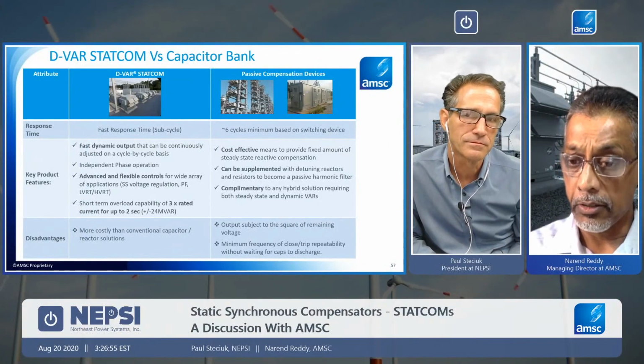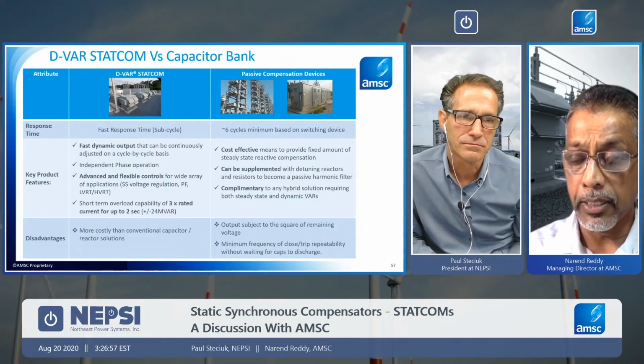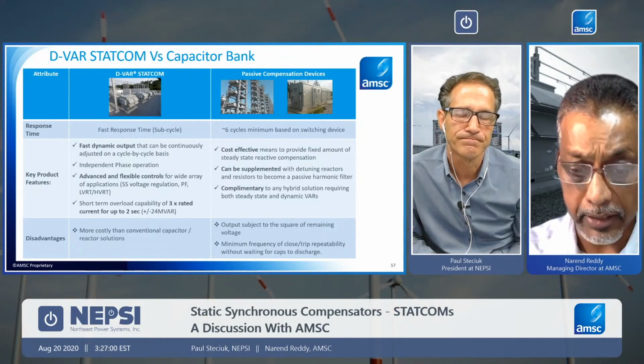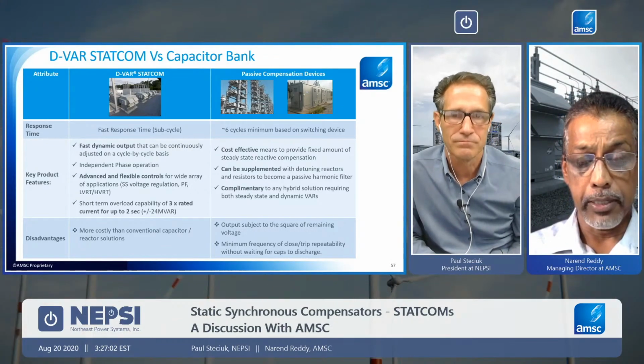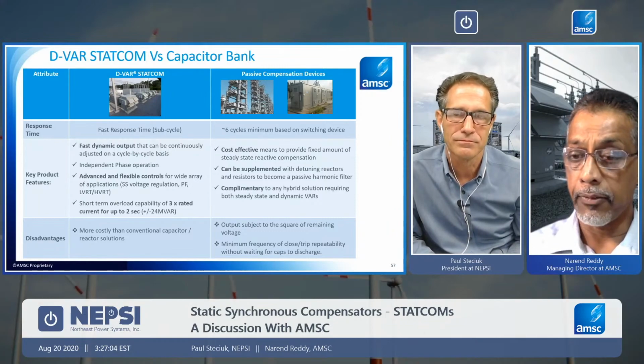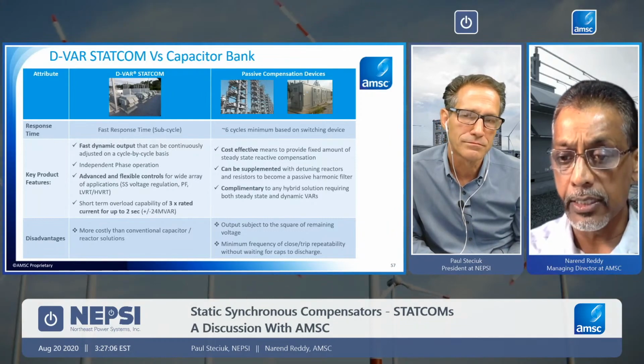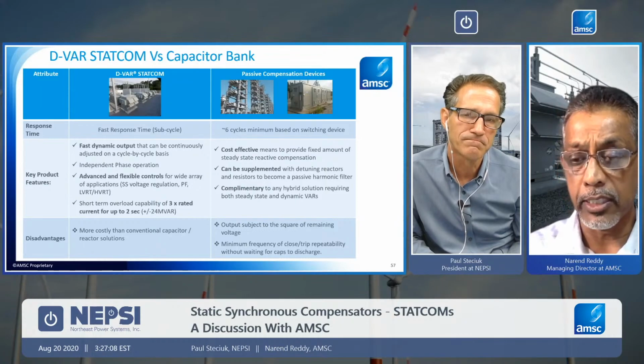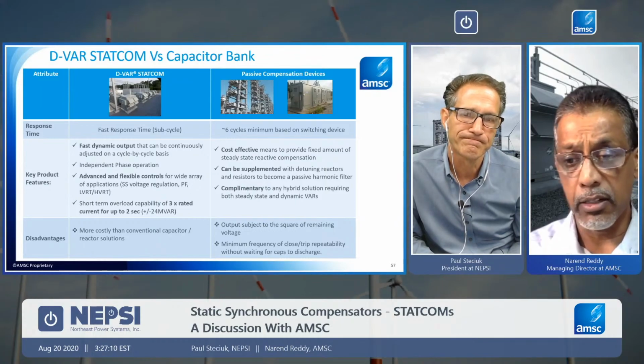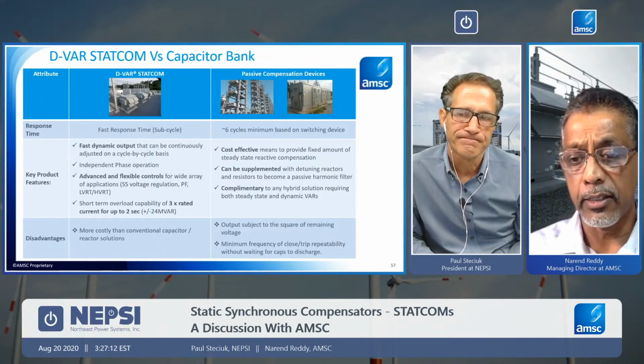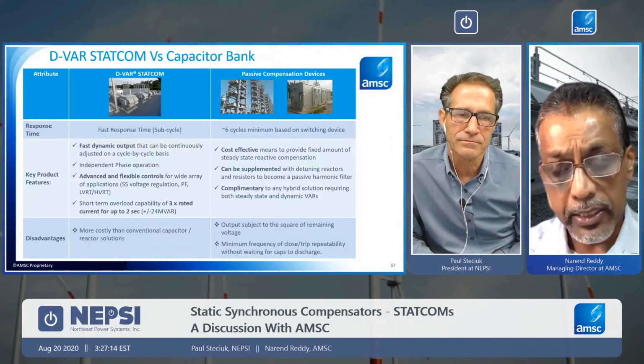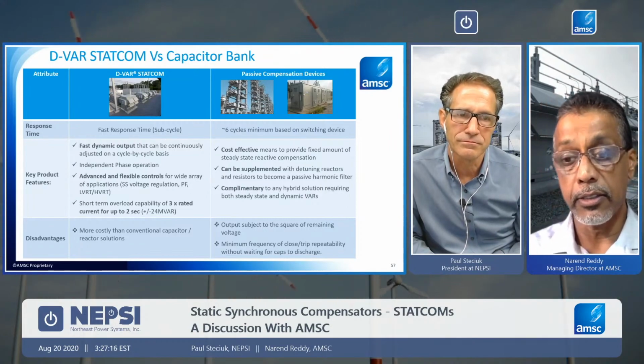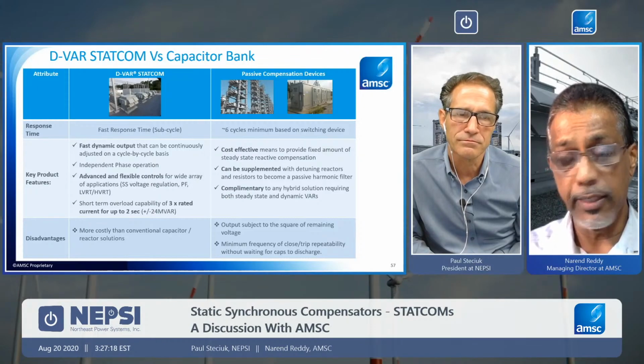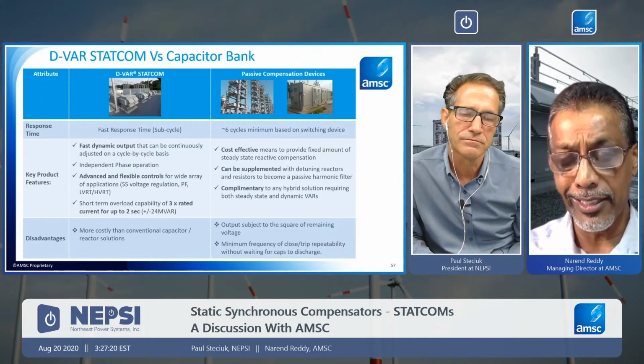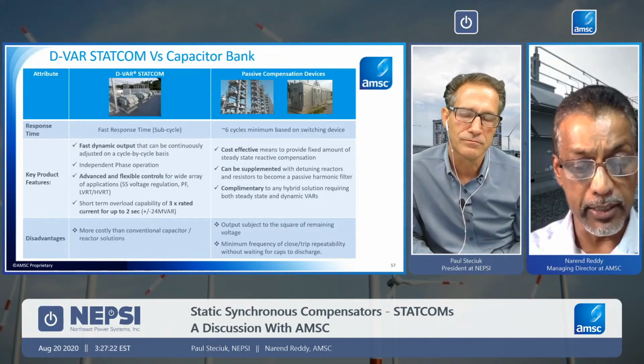Cannot be used. Really, cost would then be what's the right size STATCOM that is needed for that. But if it's not dynamic, if it's more of a steady state long-term requirement, if it's just to switch it in and no repetitive switchings are required, passive solutions are just fine and cost effective. And in that case, a STATCOM does not make sense. There's no need to spend more money on that.